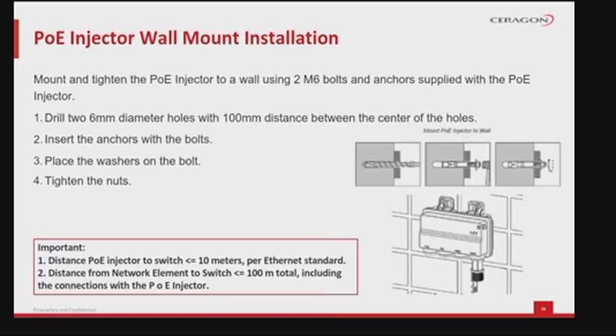This slide shows you how to mount the Power over Ethernet injector on the wall. Mount and tighten the PoE injector to a wall using two M6 bolts and anchors supplied with the PoE injector package. 1. First, drill two 6 mm diameter holes with 100 mm distance between the center of the holes. 2. Then, insert the anchors with the bolts. 3. Place the washers on the bolt. 4. Lastly, tighten the nuts.